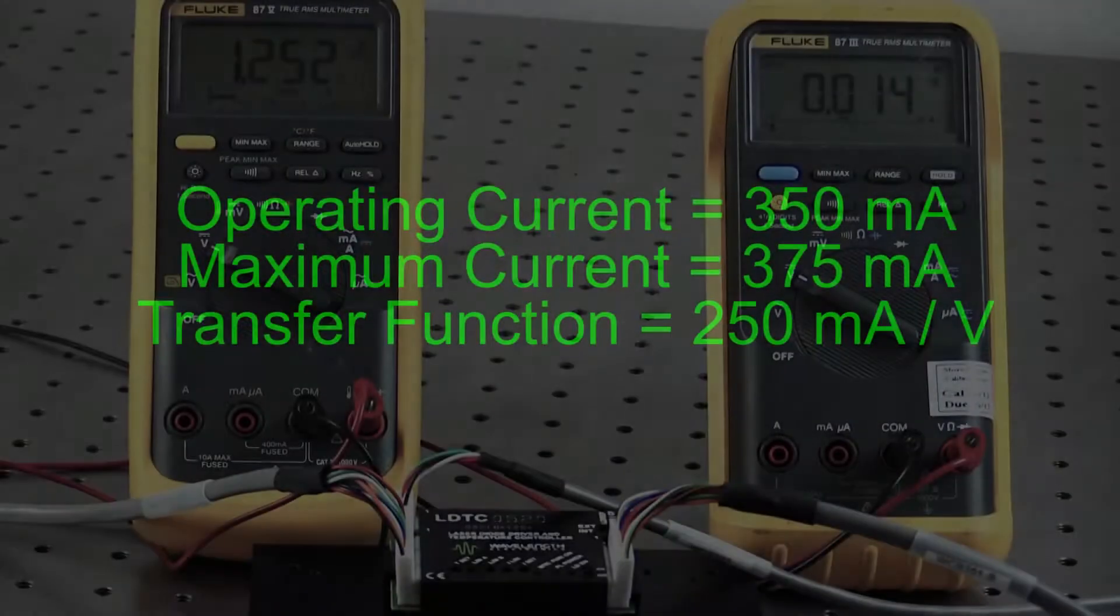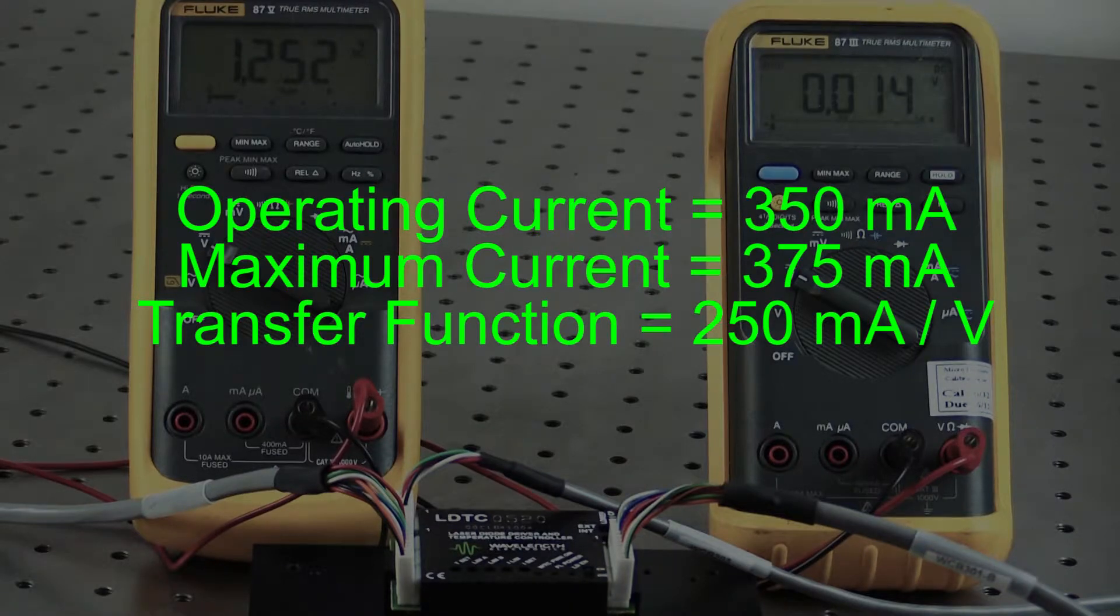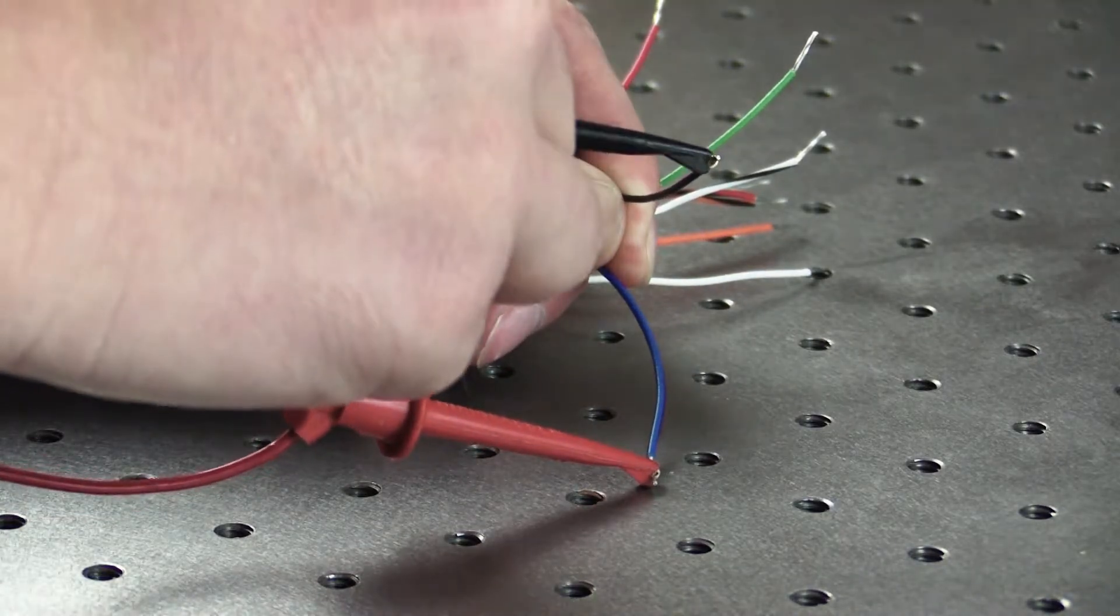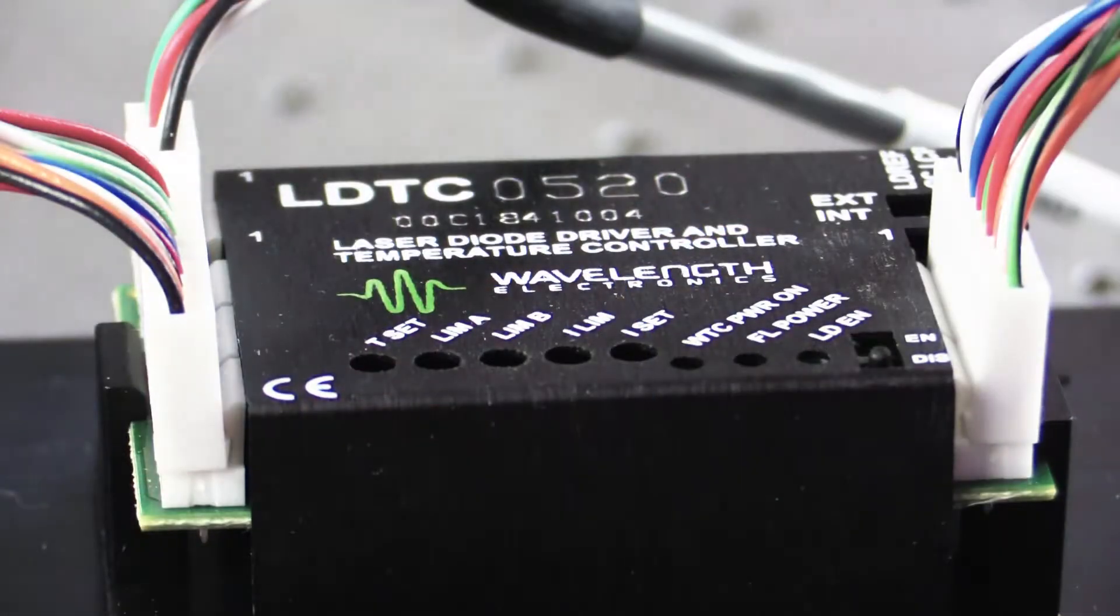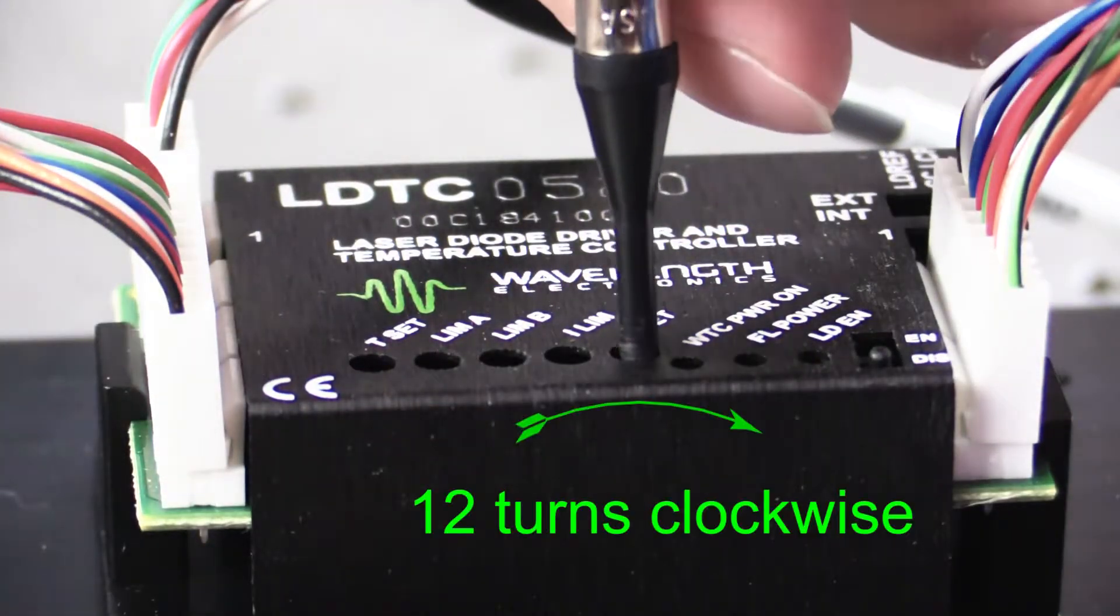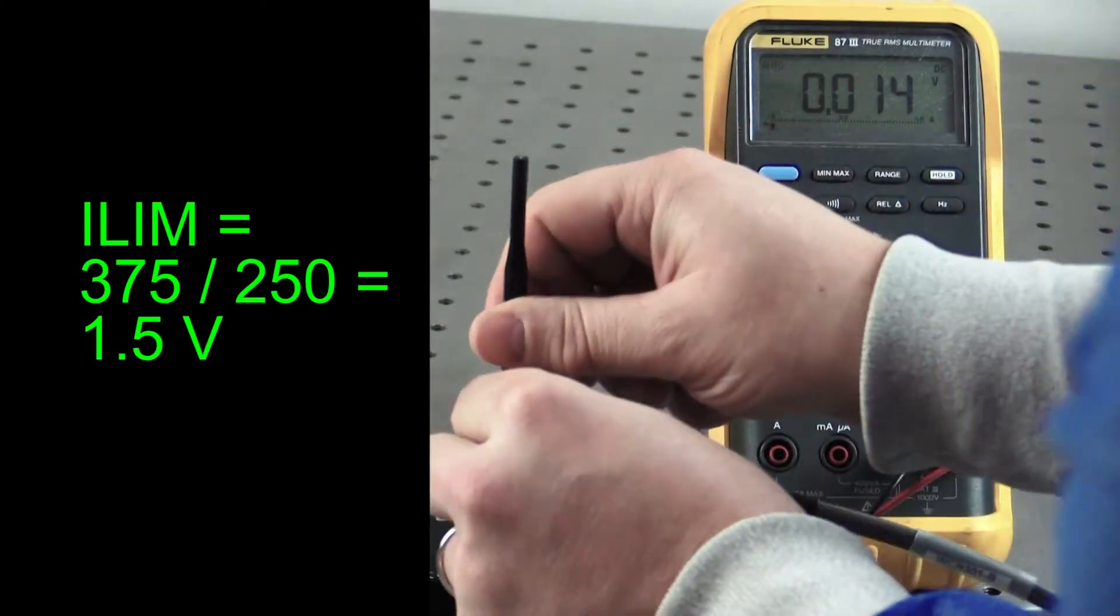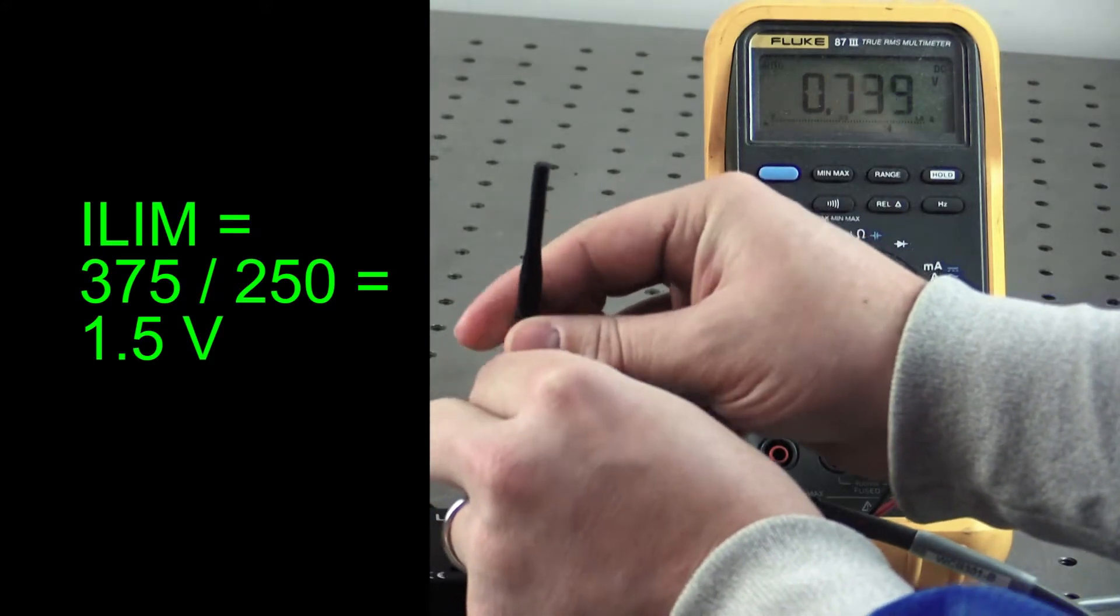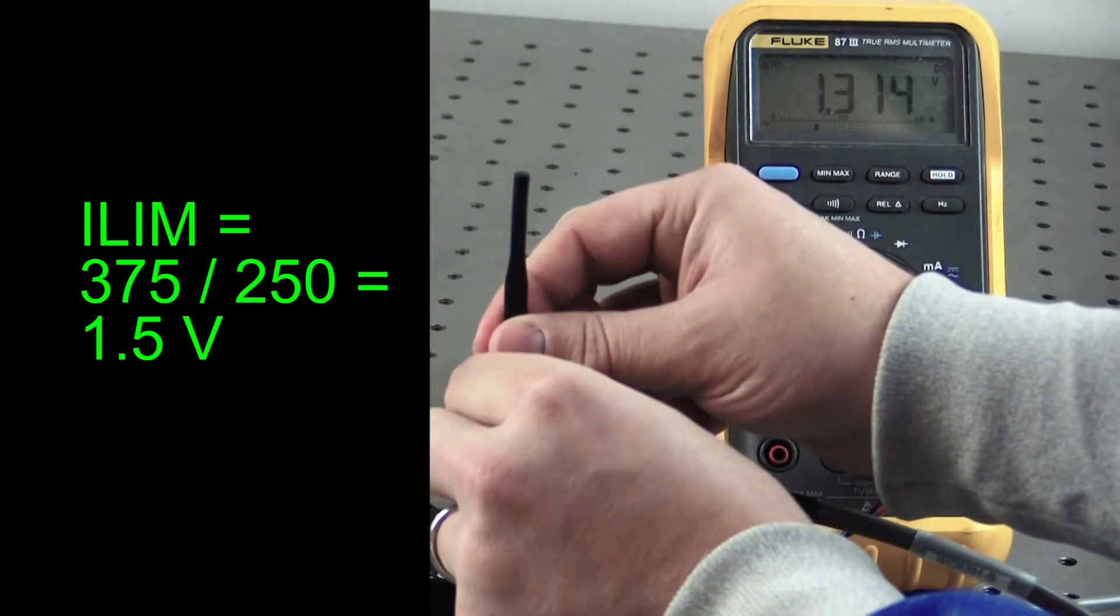We want to operate at 350 milliamps with a maximum current of 375 milliamps. The LD Imon transfer function for the LDTC0520 is 250 milliamps per volt. We will set the limit current first. Connect the multimeter to LD Imon and common. Turn the ISET trim pot fully open 12 turns clockwise. Now, adjust the ILIM trim pot clockwise until the voltmeter reads 1.5 volts. The limit is now set at the maximum allowed current of 375 milliamps.